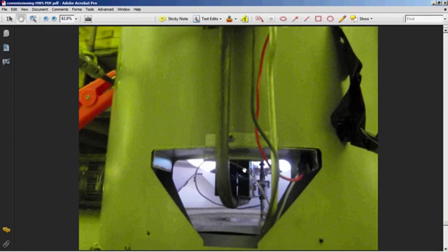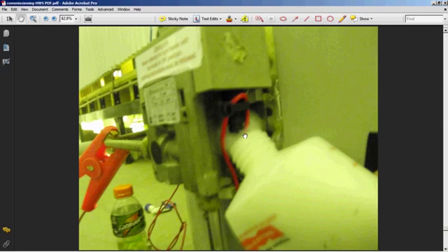So the main burner is on. And then you soapy bubble test it. You need to make sure you soapy bubble test that test point screw, because the same as the gas valve, if you don't test it now, it'll go untested, and if it's leaking, it'll leak forever. You also need to make sure the main burner is going, because if the main burner isn't going, that test point screw isn't going to leak because there's no pressure behind it.